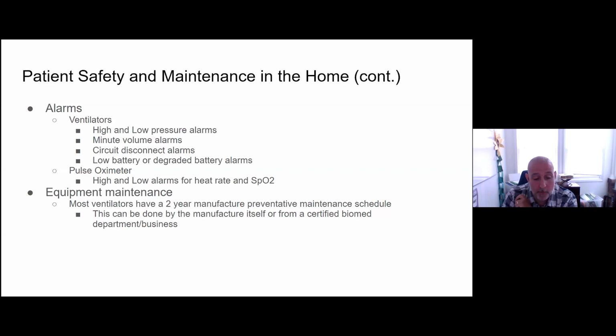There's also a minute volume alarm. If you set the parameter and the therapy doesn't hit the minute ventilation, it usually means there's a leak, and that could also be effective. There's a built-in circuit disconnect alarm, so if the circuit becomes disconnected for whatever reason while the patient's using it, it'll notify the caregivers, and that could be a little more sensitive than the low pressure alarm. That would be effective, especially if they're using the equipment at night. You'd want to know that the mask came off or the tubing came off.